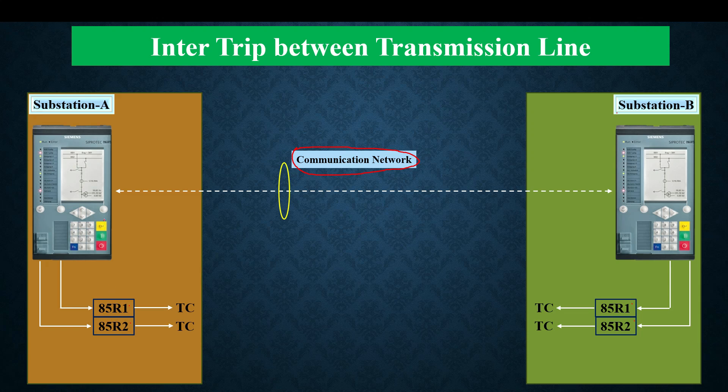For example, if single-phase differential protection operates it will go to 85R1, but if two-phase or three-phase differential protection operates it will operate 85R2. All this logic must be configured in the concerned protection relay — specifying which signal will operate 85R1 and which will operate 85R2.